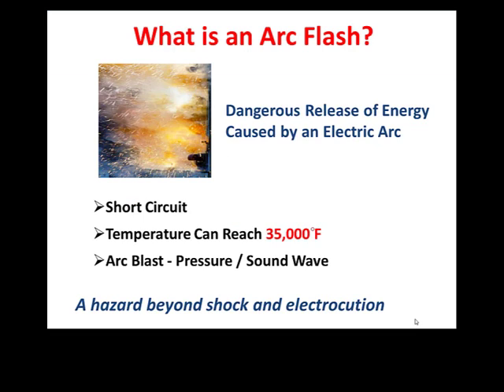Shock and electrocution are recognized electrical hazards when working with 50 volts or more. Arc flash is the other hazard that has received quite a bit of attention since the early 2000s when working with electrical distribution systems and equipment in buildings and facilities. Have you ever shorted out anything and experienced a flash for a fraction of a second? Like using jumper cables, maybe? That's an arc flash where there is not enough energy available to sustain the arc. An arc flash is a short circuit with enough voltage and current to maintain an arc.